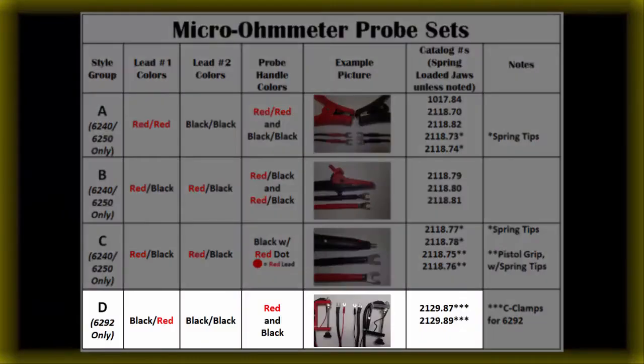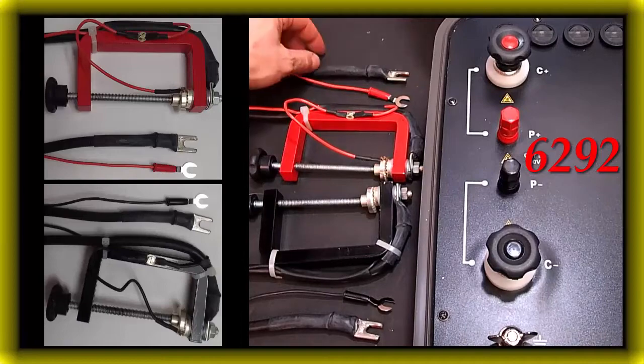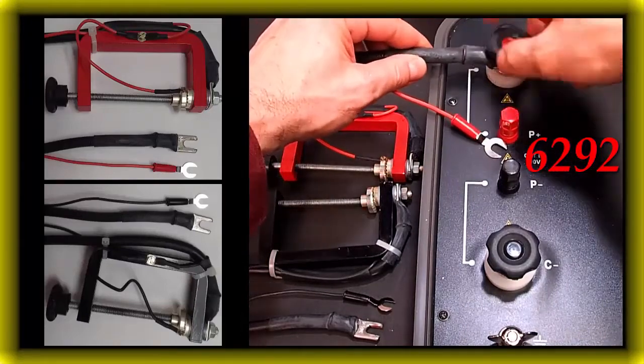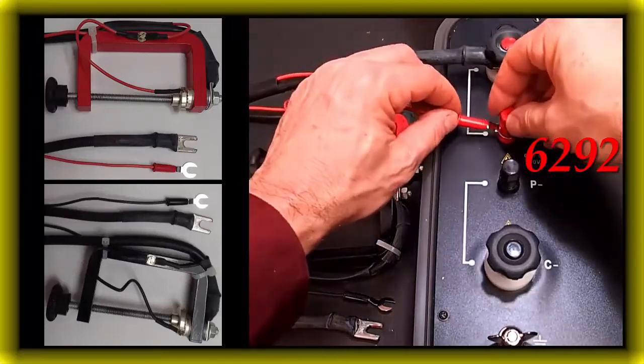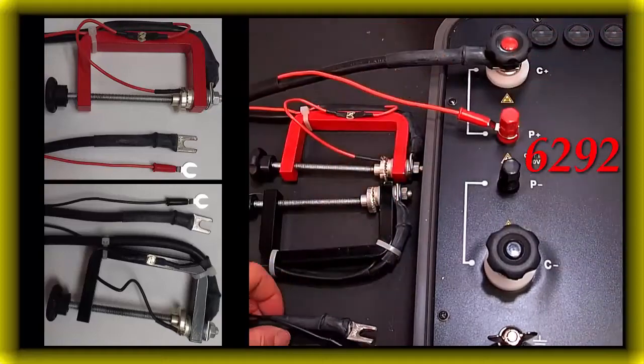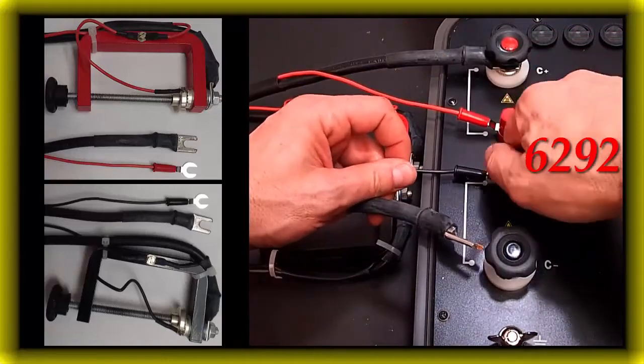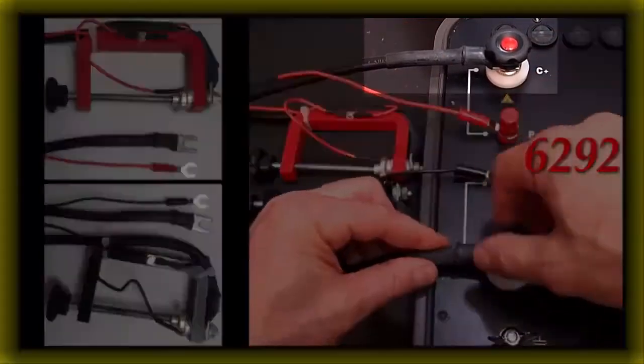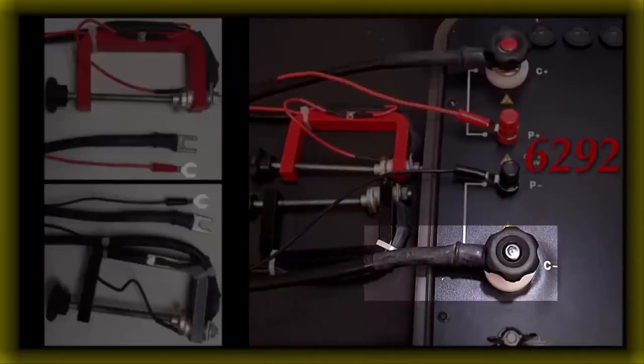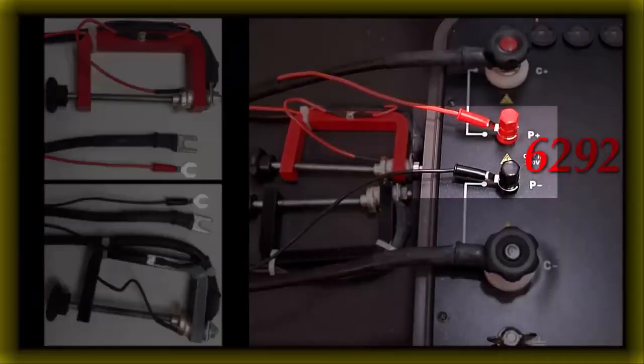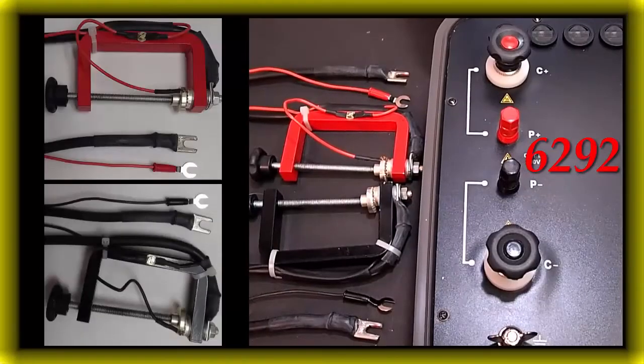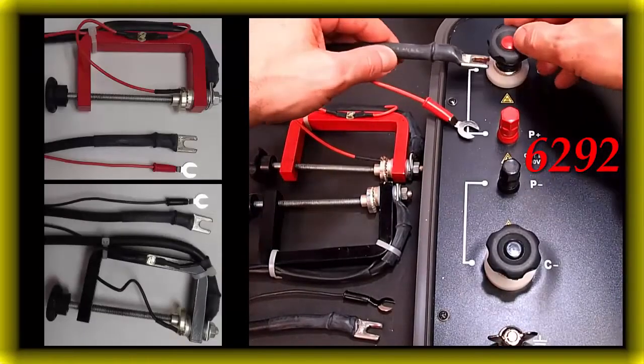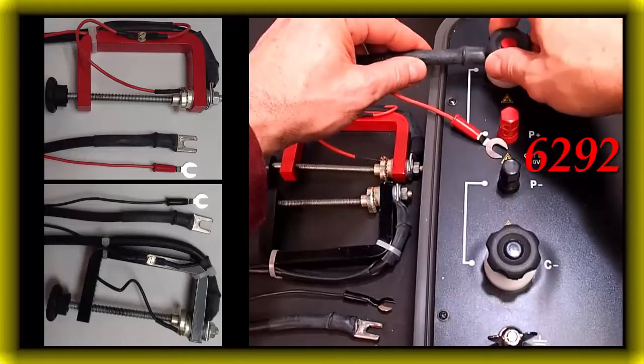Style Group D for 6292. When using the 2 part numbers from Style Group D for the 6292, the leads are black, red, and black, black, and the probes are C-clamps rated for 200 amps. The connections will not match the color coding on the meter's terminals. In this case, the thicker black leads will always connect to a C terminal, and the thinner red and thinner black lead will always connect to a P terminal. These leads are designed specifically for the 200 amp 6292.